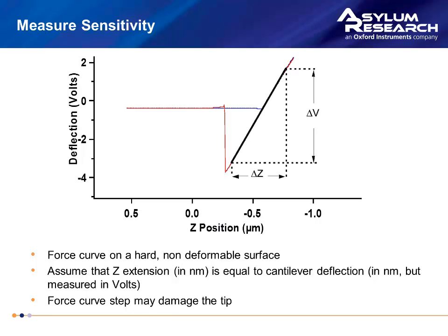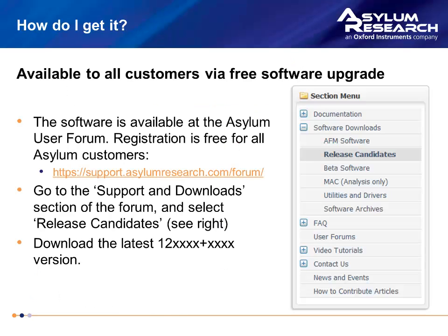The main drawback of this technique is that if we have a very sharp cantilever, it's usually damaged during that first force curve. Or if we have a cantilever that is chemically functionalized, we can actually damage or foul that chemical coating during that first force curve. Additionally, sometimes you might have a sample that does not have a stiff region where you can do your InvOLS force curve, and this is very common with biological and polymer samples. The GetReal method we'll show you today is a great way of circumventing all of these issues.